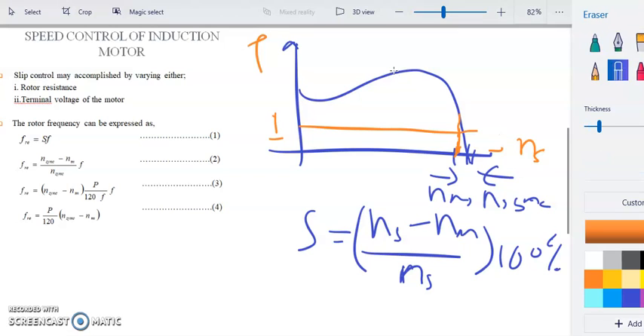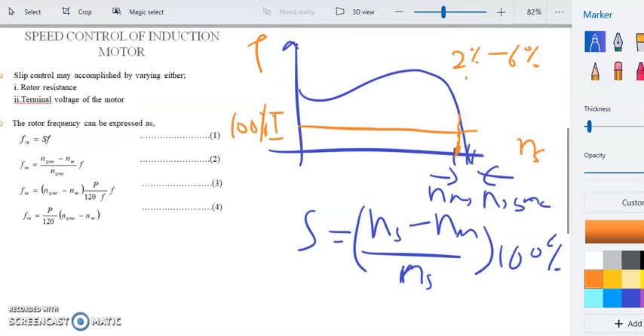So the rated current will always happen here. This is 100% of your rated current. During starting, the current or the torque will be much higher compared to the rated one. But once it reaches steady state, this should be your speed, within this range. That's why I told you the range of your slip is between 2% up to 6%.